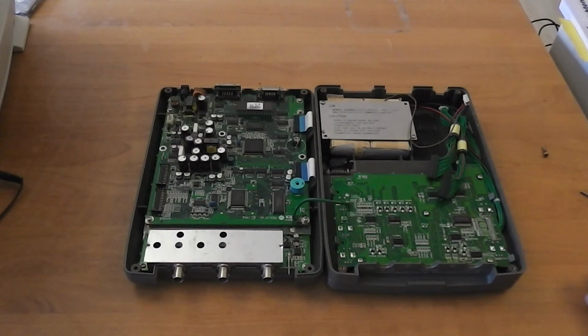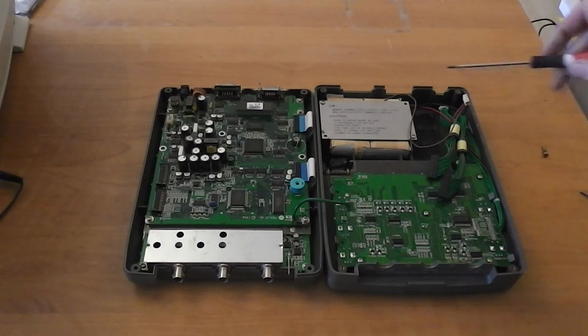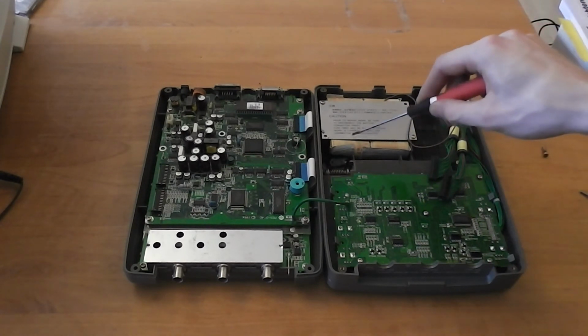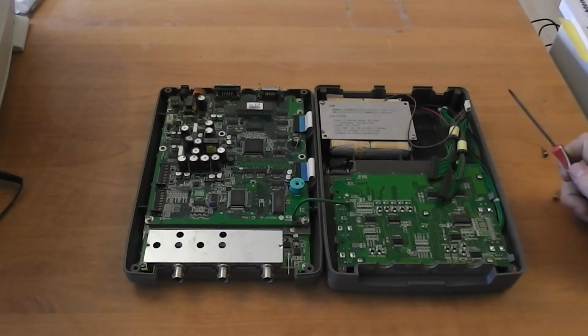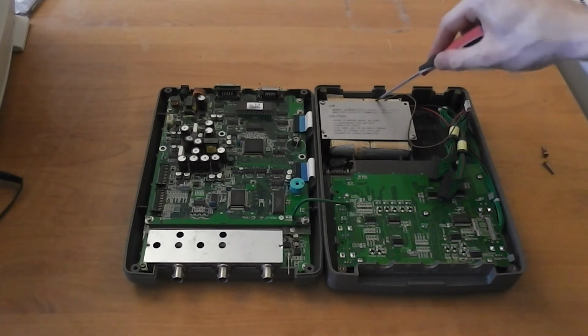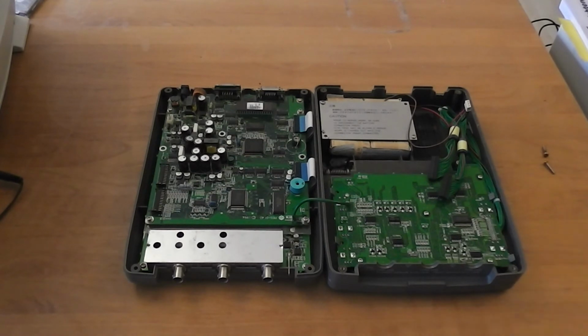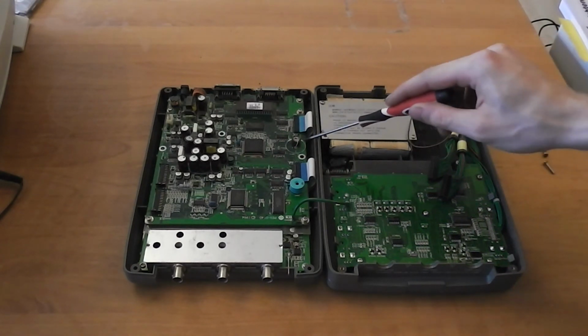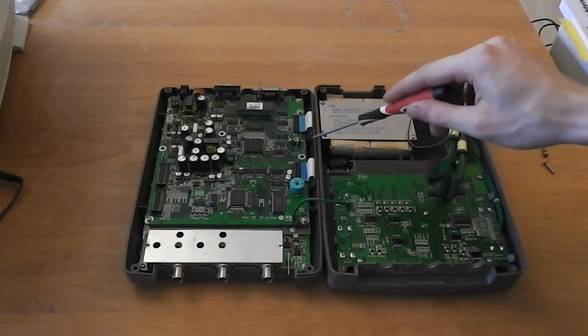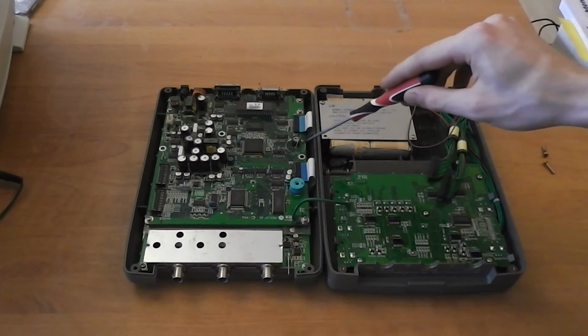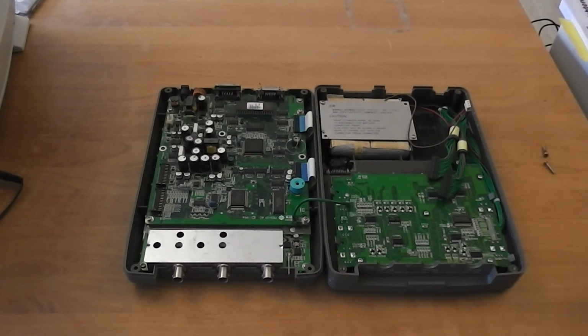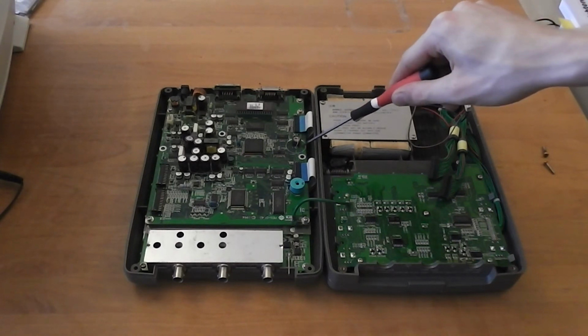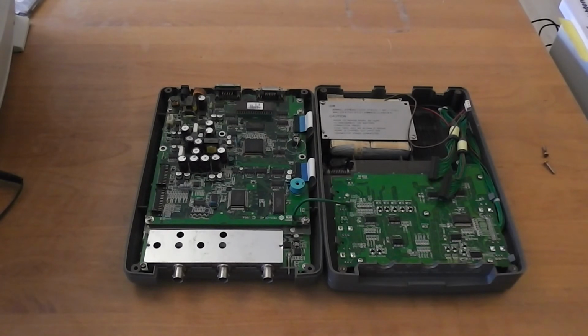So it's at least 3 board construction. So of course you have your battery pack here, which I also already repaired and patched a little bit. I took 2 cells out which were leaking and put some other, I think also dead cells in. This battery is lasting for like 20 seconds, but better than nothing. And well, I also already botched in another super cap, since the one which was in here was faulty, and that's what's holding the calibration data. So yeah, calibration on this thing is messed up anyway, but if this is completely dead, then you will have to wait like 2 minutes when it's booting up every time.